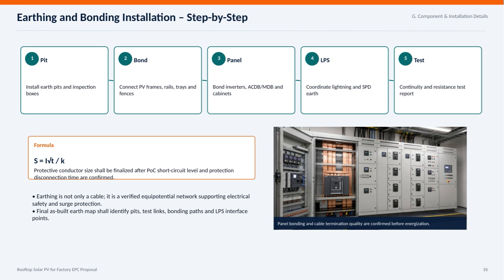The protective conductor size is determined using the formula S equals I times the square root of t, divided by k, with the size finalized after PoC short circuit levels and disconnection times are confirmed. Remember, earthing is not just about running cables. It's about creating a verified equipotential network that ensures electrical safety and surge protection. The as-built earth map should clearly document pits, test links, bonding paths, and lightning protection system interface points. Before energizing the system, we confirm the quality of panel bonding and cable termination to guarantee safe and reliable operation.